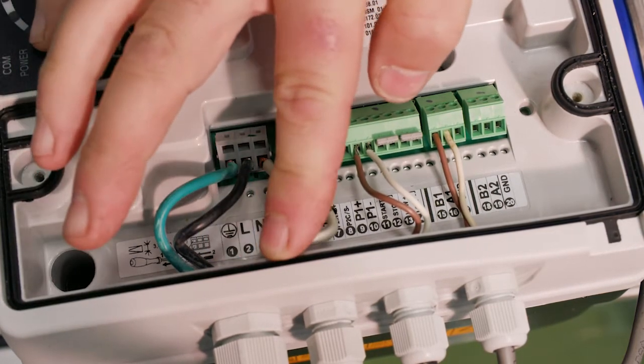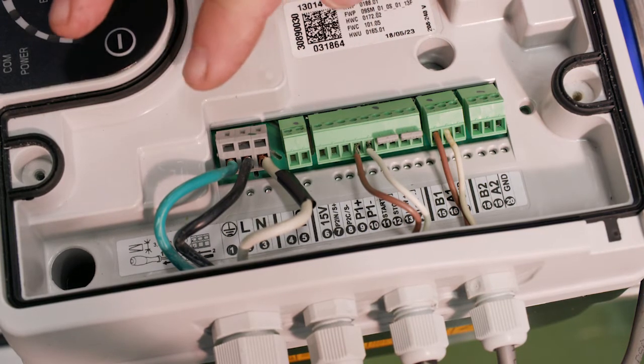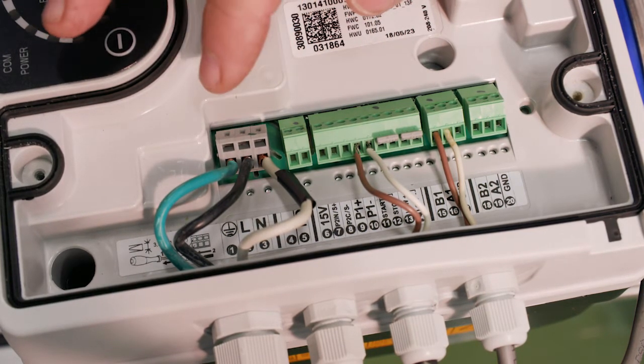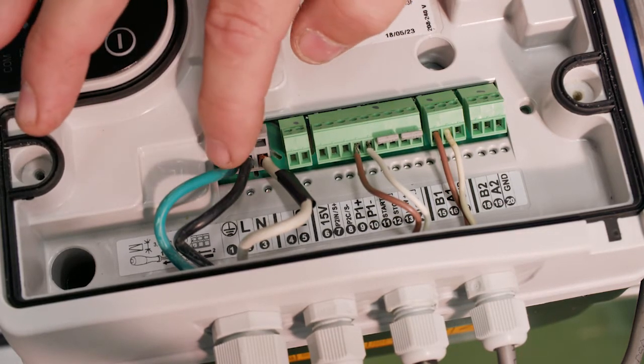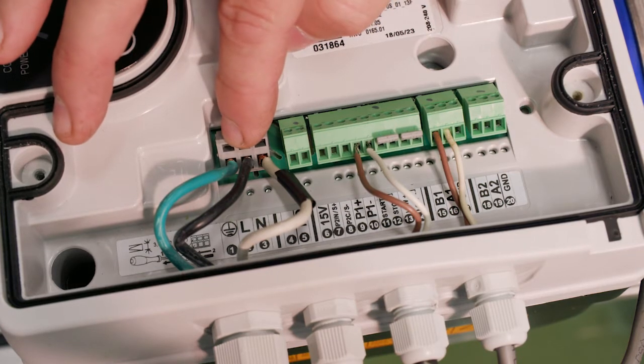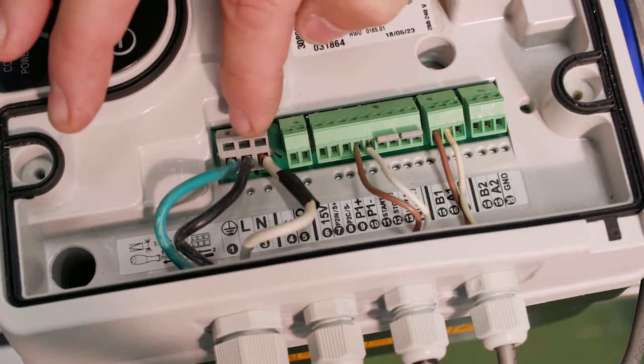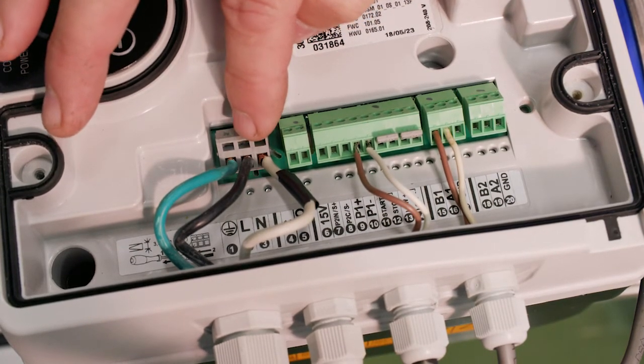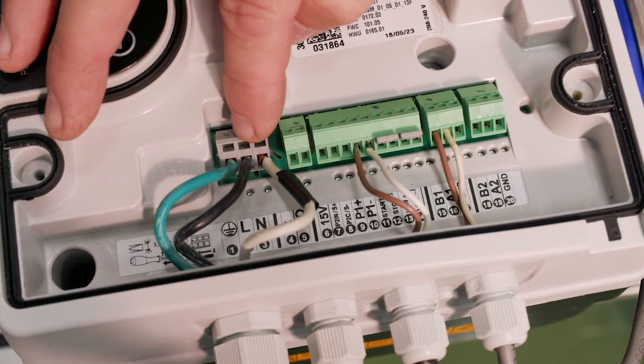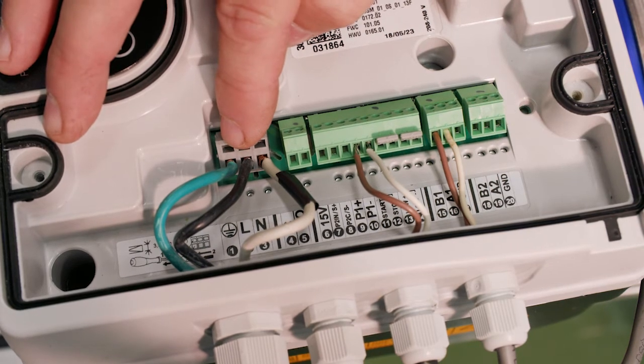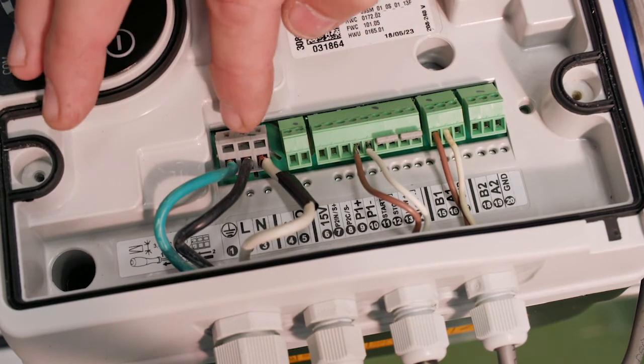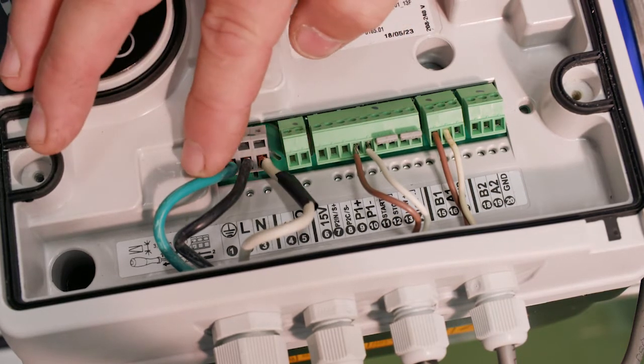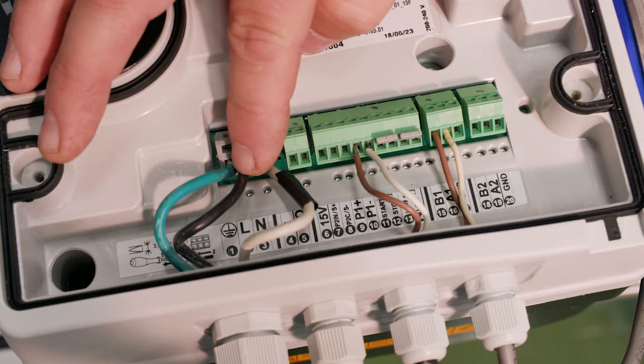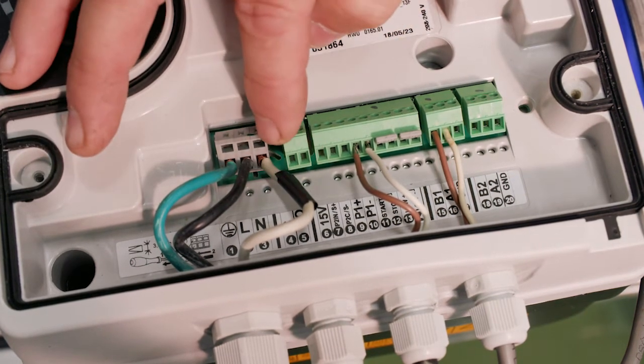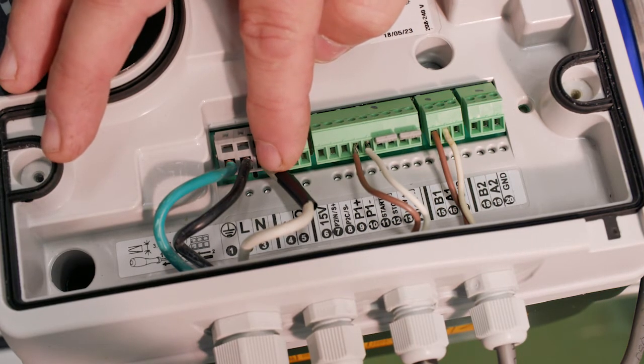If we look here, typical type of terminal board, we see the input power on the left-hand side. What's a little bit unique about this is we see a ground on terminal 1, one line on terminal 2, and then a neutral on terminal 3. Now the nameplate says 208 to 240 volt, and in this case we do have 240 coming in, regardless of the color. That's why we put some black tape to remind us that we do have 2 hots and a ground. So you simply connect one of the hots to line and the other hot to what is labeled neutral here, and we have a ground.